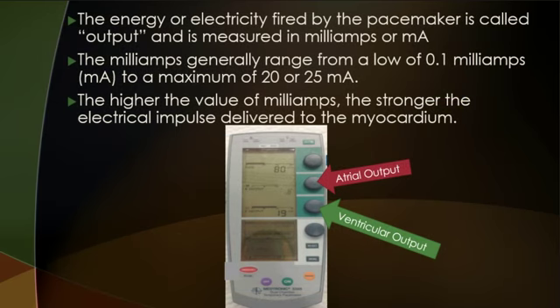So energy, or electricity fired by the pacemaker, is called output. It's usually measured in terms of milliamps, or mA. The milliamps generally range from a low of 0.1 milliamps to a maximum of 20 or 25, depending on the generator you're using. The higher the value of milliamps, the stronger the impulse delivered to the myocardium. So you always want to use the least amount of output that you can to generate electrical activity in that patient. As you look at the picture, this is what our Medtronic looks like, and I have arrows on the atrial output and the ventricular output.